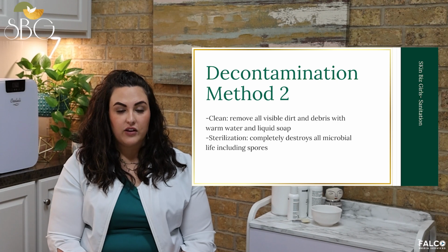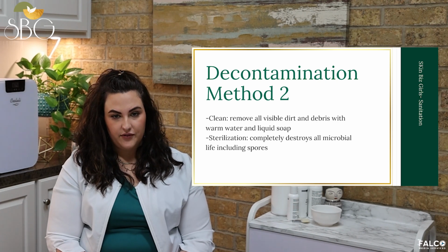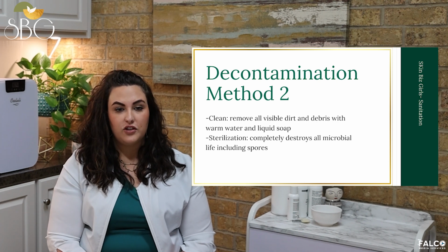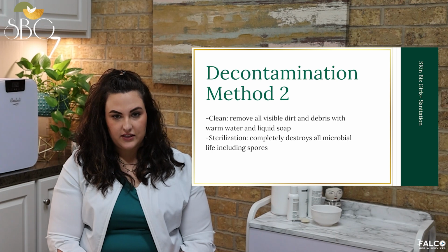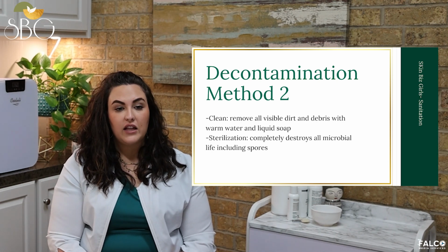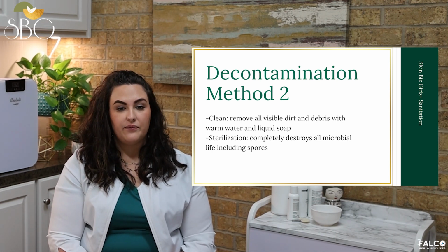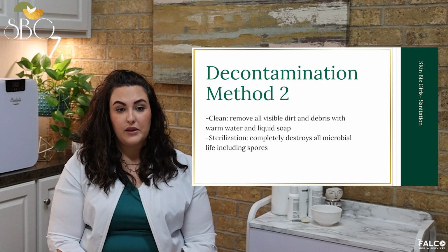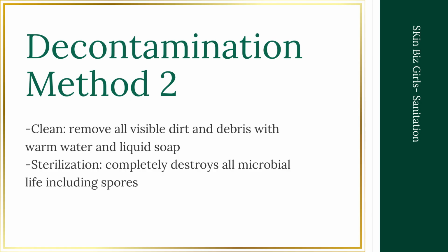High-pressure steam autoclaves are most effective. These devices require weekly testing to ensure they're working properly by means of a spore test. If your autoclave is not working properly, instead of sterilizing your tools, you may in fact be creating a breeding ground for organisms to thrive.